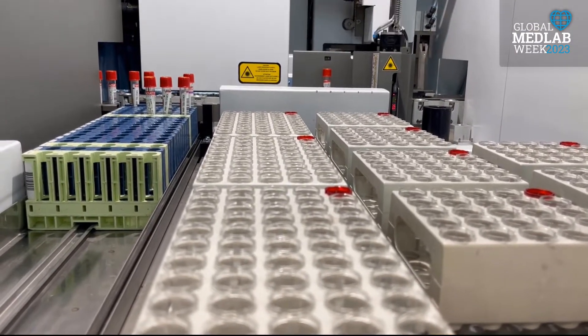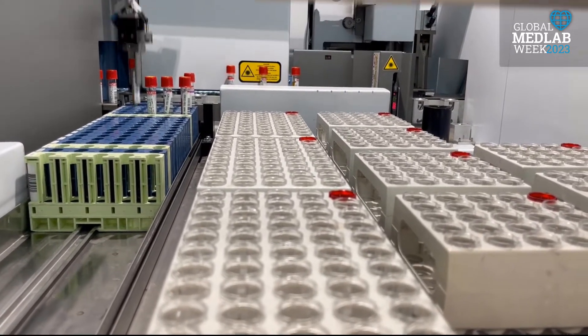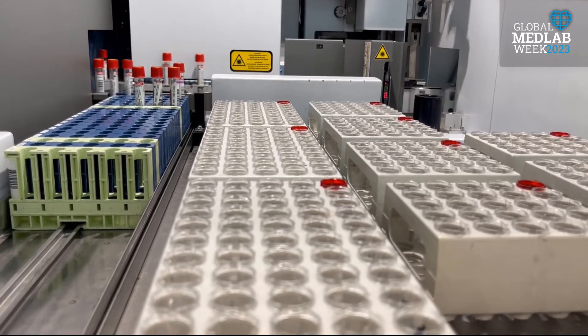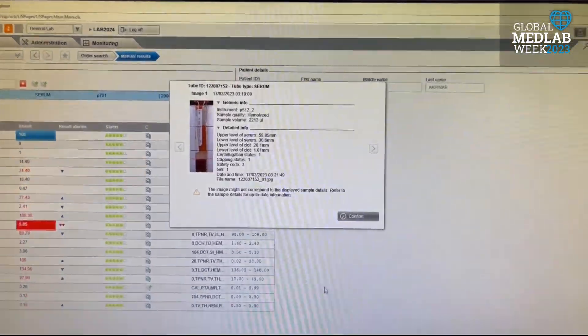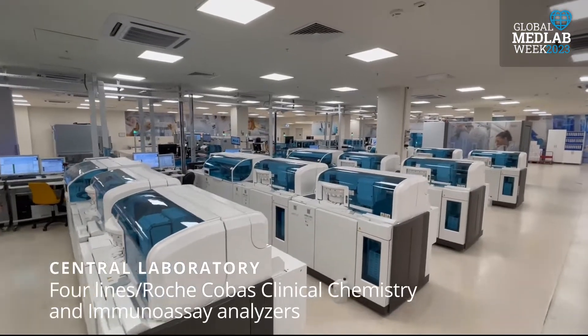Inappropriate samples are rejected on a sample or test basis. By way of the QSI camera in the Pre-Analytical Module, all samples are evaluated with the hemolysis, icterus and lipemia index and saved as photographs to the middleware, and inappropriate samples are separated to the error box.